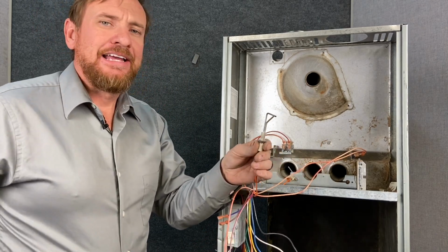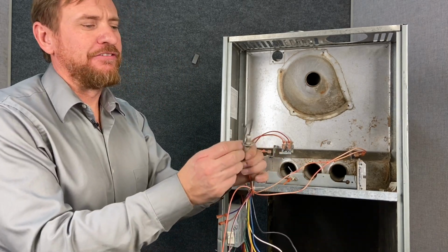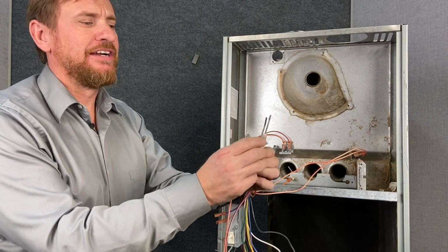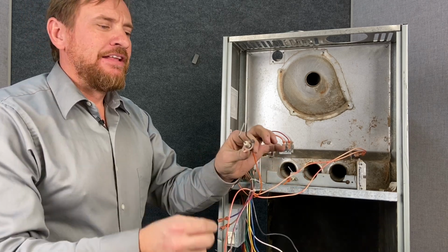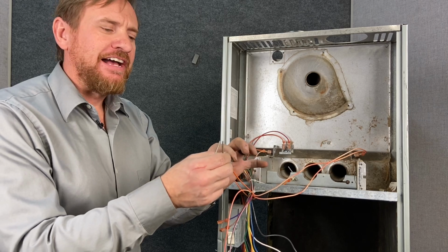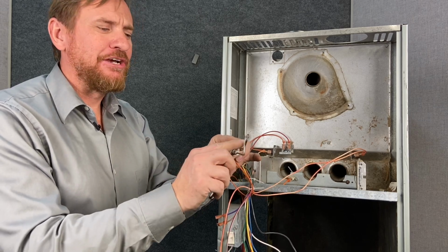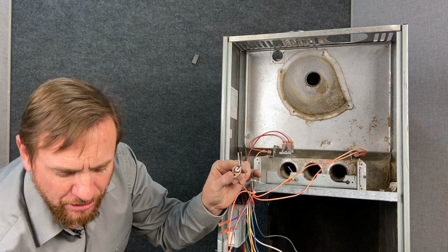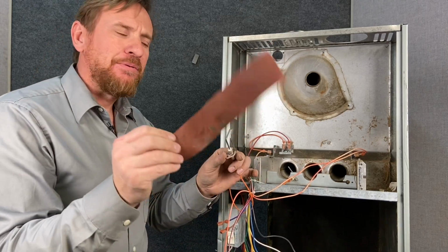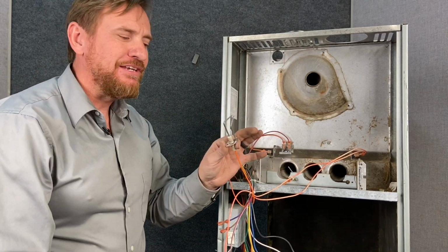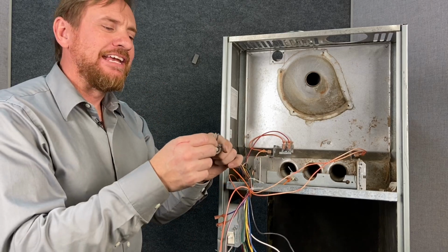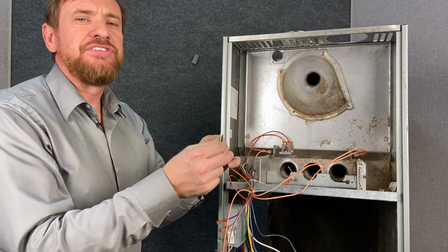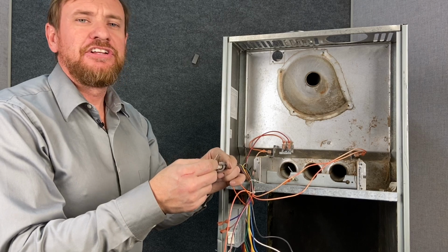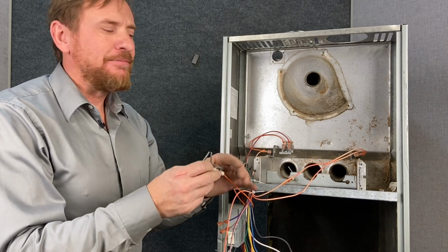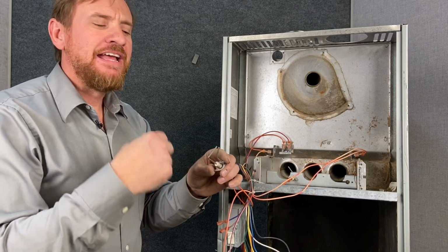Now this is our spark igniter. This is going to be a high maintenance component right here. If there's a lot of little black pieces on here, what we're going to want to do is clean that. Now this is where we're going to use a soft style Brillo pad to clean this to make sure we get all of that black off of there. We never want to use sandpaper or sandcloth on this. This is not what we use. The reason is the sand can gouge into and leave grooves in this. Also, it can leave the silicone coating on that.